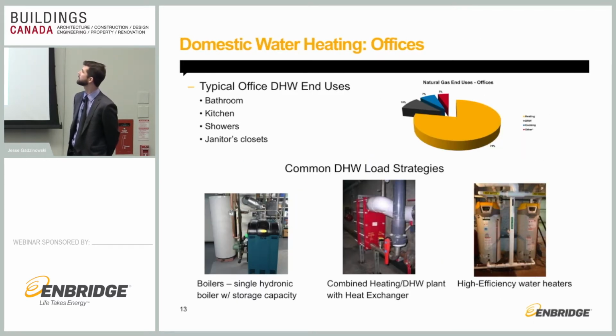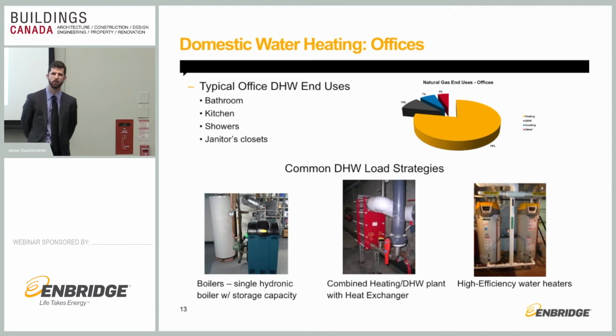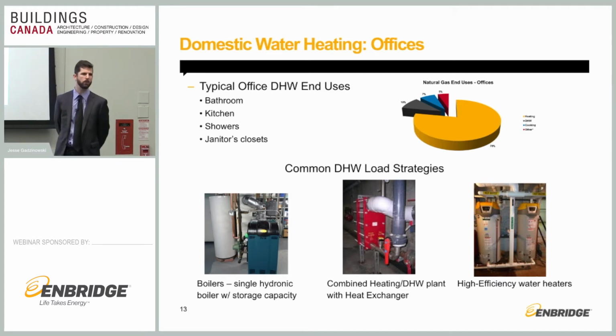So domestic hot water, the second chunk, if you remember from the pie chart, is only around 10%. In office buildings specifically, it's not a large concern generally. I go into a lot of buildings and the heating systems are brand new, the BAS is brand new, but you'll still have a 25-year-old boiler for the domestic hot water just chugging away. And they're like, well, it's working fine, it doesn't really need a retrofit yet. But really, if you're consuming 200,000 cubes in a building and only 10 or 15,000 cubes of that is domestic hot water, it makes sense that it's not the biggest point for the retrofit.